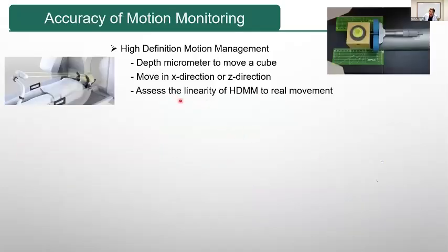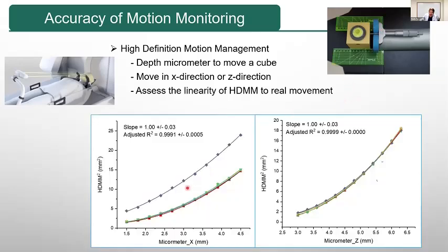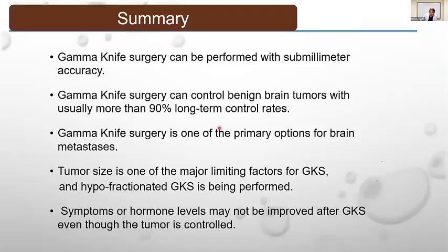And the final one is I checked the high definition motion measurement system. I made this tool with tape and rulers. It looks ugly, but it worked very well. I adjusted the motion of this cube with depth micrometers, 0.05 millimeter accuracy. And this one shows the relation between high definition motion measurement and actual motion. The proportional slope of this was 1.00 for X, Y and Z directions. It looks very good. So this is my last slide.